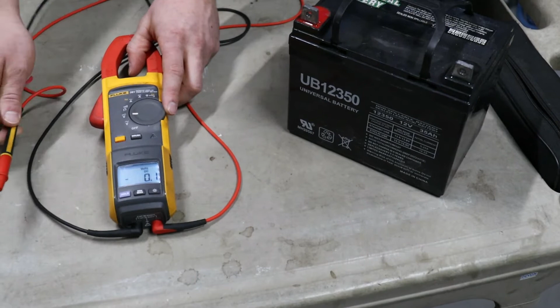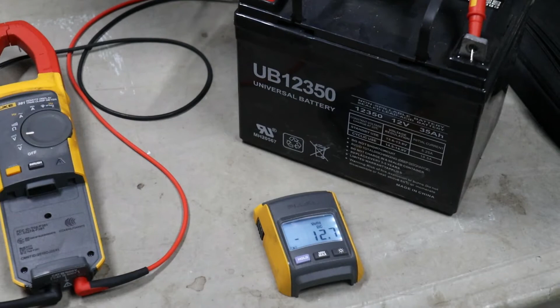So that's how you test DC voltage. Black with negative, red with positive. And with the remote display, I'll give you a little example of that. So we'll take that off and we'll test the battery here again. And no problem. Like I said, up to 30 feet away you can go with that display and it'll still give you a perfectly accurate reading. And while we're on the DC battery part, I'll show you if you happen to reverse the leads, it'll give you a negative voltage. So if I put red on black and black on red, you got negative 12.7 volts.